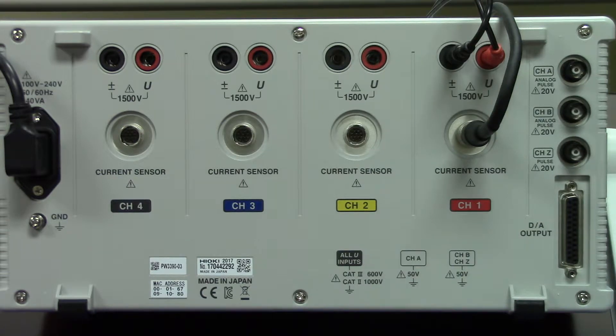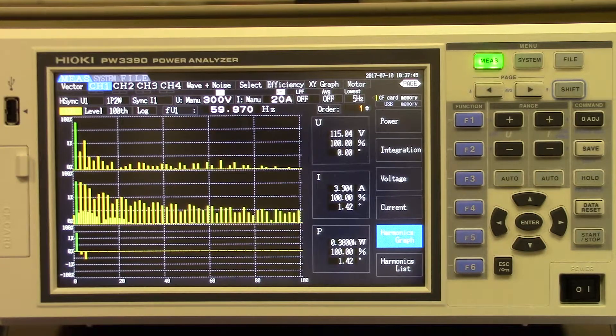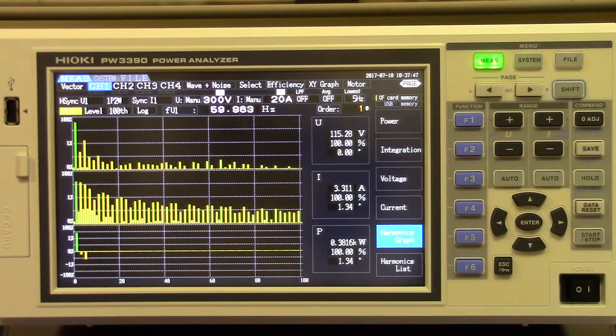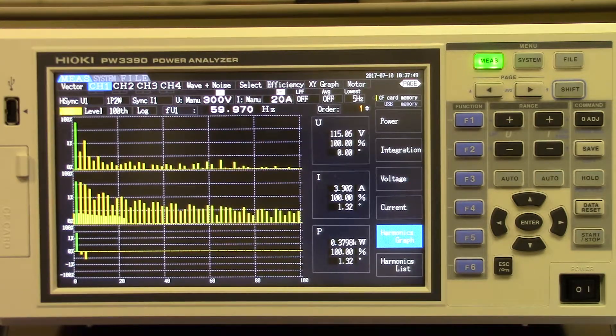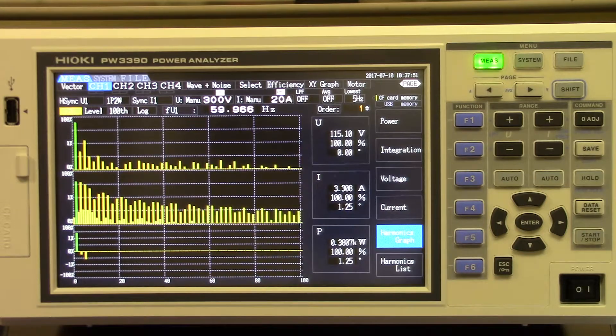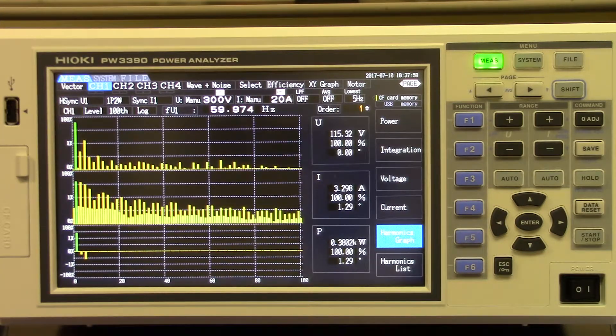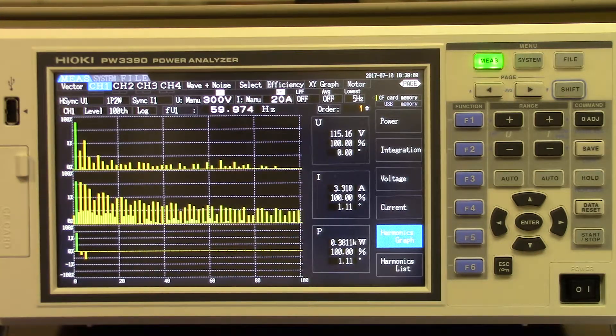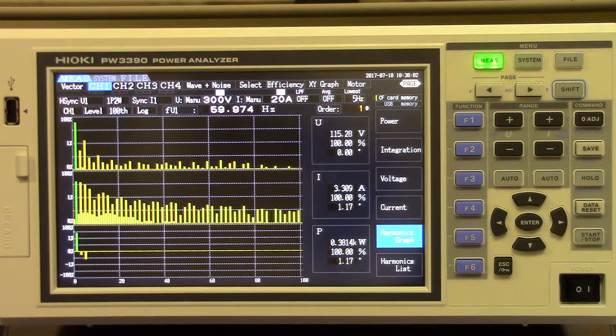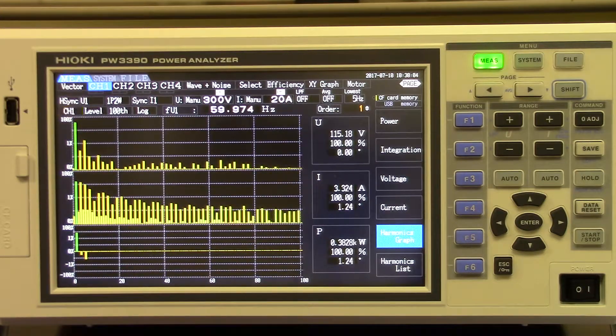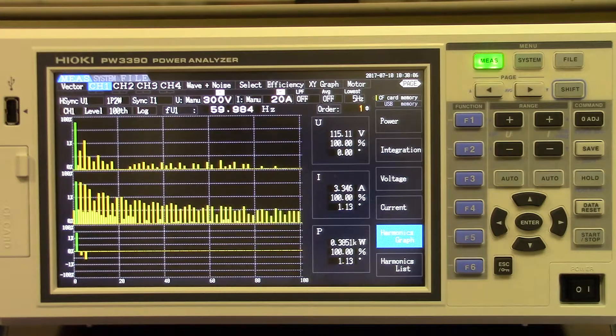A D to A option is available as well. The screen is a 9-inch TFT LCD display and the unit's basic accuracy is plus or minus 0.04% of the reading plus the accuracy of the current clamp being used. We have developed a new series of current clamps that offer wider temperature range capabilities while maintaining the highly accurate readings associated with the Hioki brand current clamps.